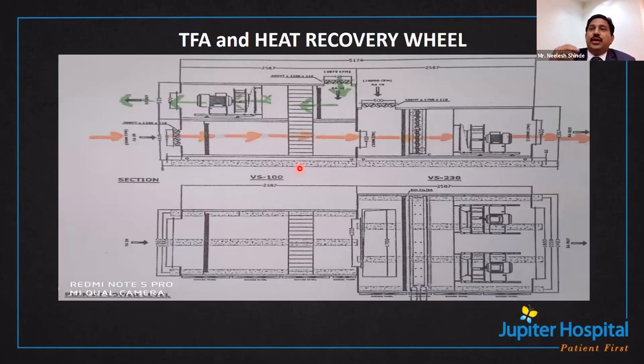Now this is one more thing we have introduced in Pune: treated fresh air and a heat recovery wheel. As I told you, in Pune in winter the temperature most of the time goes to 8 to 10 degrees, and we have utilized that. In all the typical floors where the patients are, the wards, we have treated fresh air with a heat recovery wheel. The fresh air is taken from here, and there is a heat recovery wheel. If 8 or 10 degree air is coming inside, there is no need to use the chilled water coil. That same air can be treated and sent directly to the respective departments or wards. This is the real advantage of treated fresh air with heat recovery.